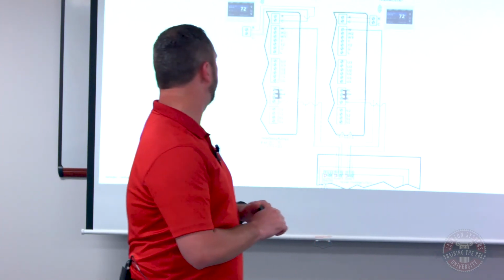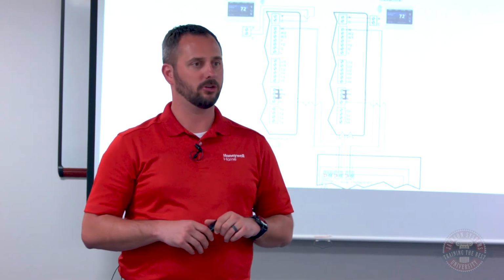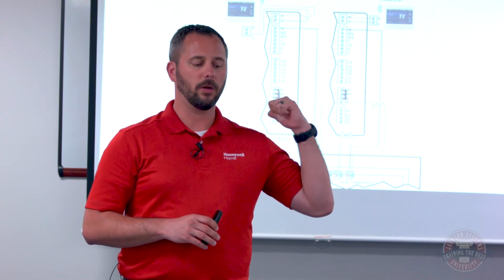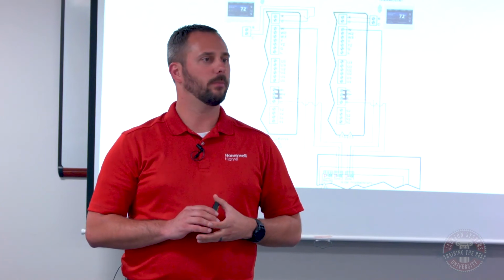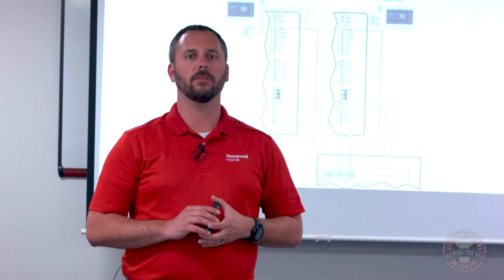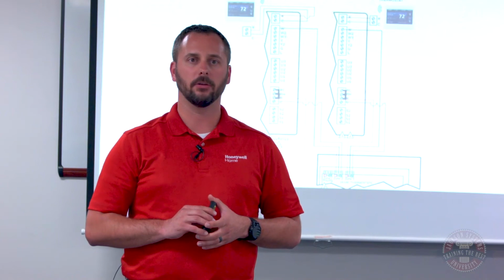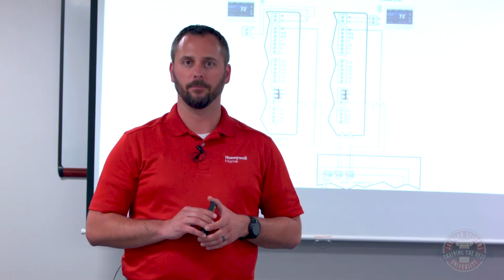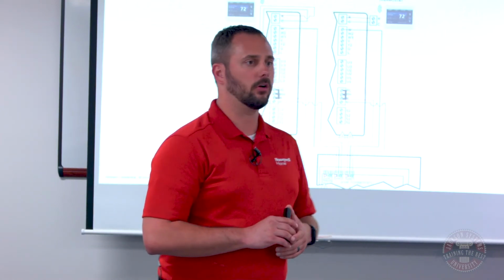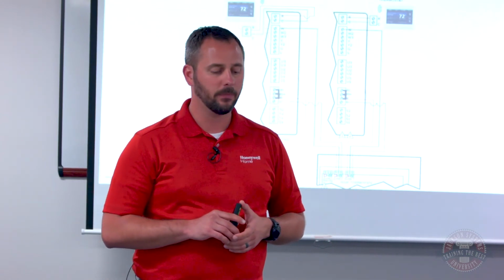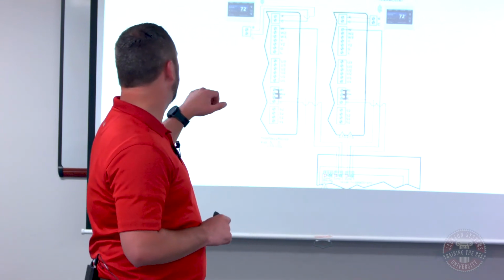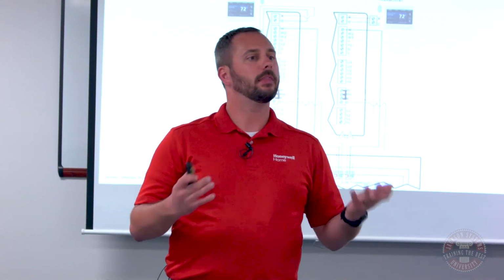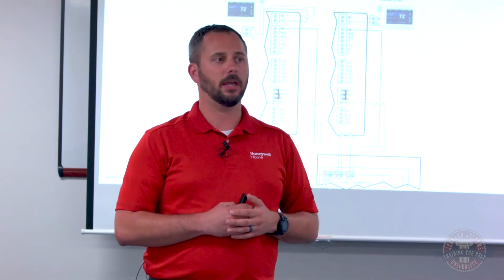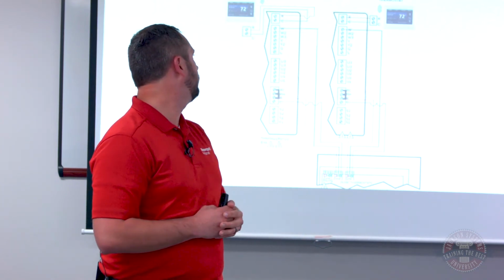So in the very small image down at the bottom, I've got a picture of our hydronic panel. This is our equipment interface module going to a Prestige. So this is one of the options for using 2 wires to get onto a connected system. Those 2 wires across the top that are marked R and C, all that's doing is literally throwing power to the thermostat. Those other 3 wires that you see there, C, R, and W, that's what's basically making the call to the hydronic panel, and that's what's powering up the board as well.